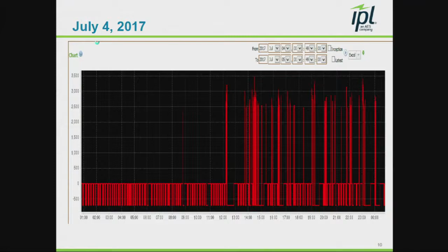One more example, maybe. A weird day, this was July 4th, where system frequency was continuously too low for the entire period. I hadn't seen one of those before. The only time I would see my battery go to 20 megawatts is when a nearby generator would trip.